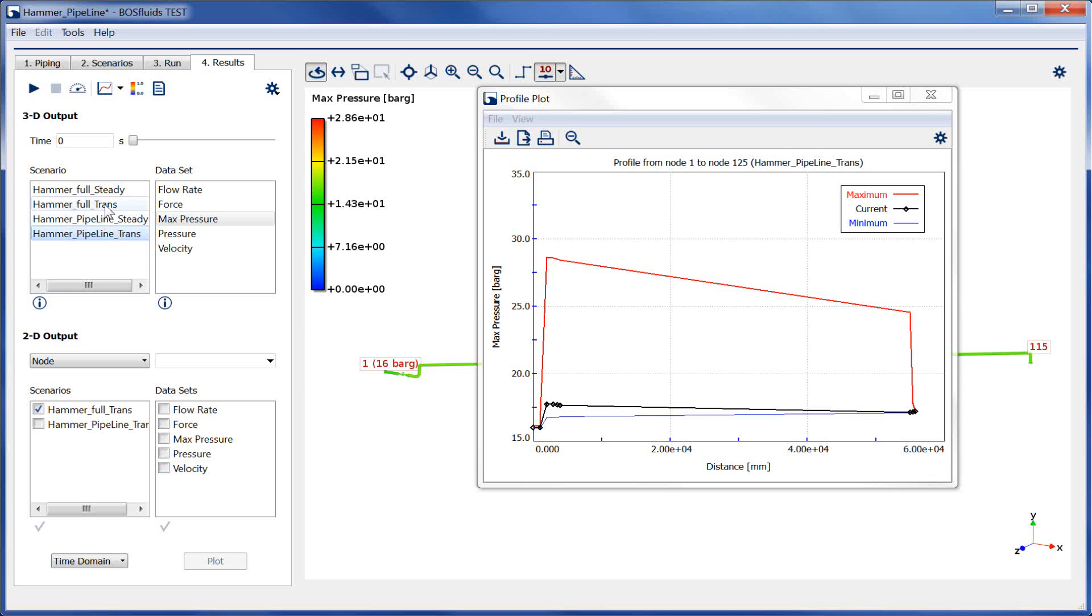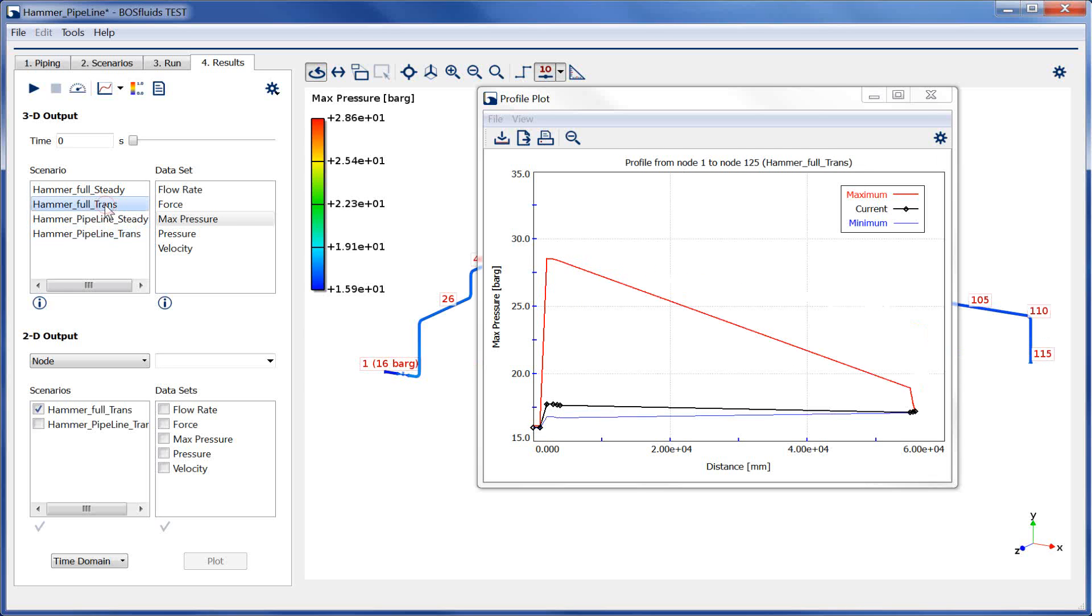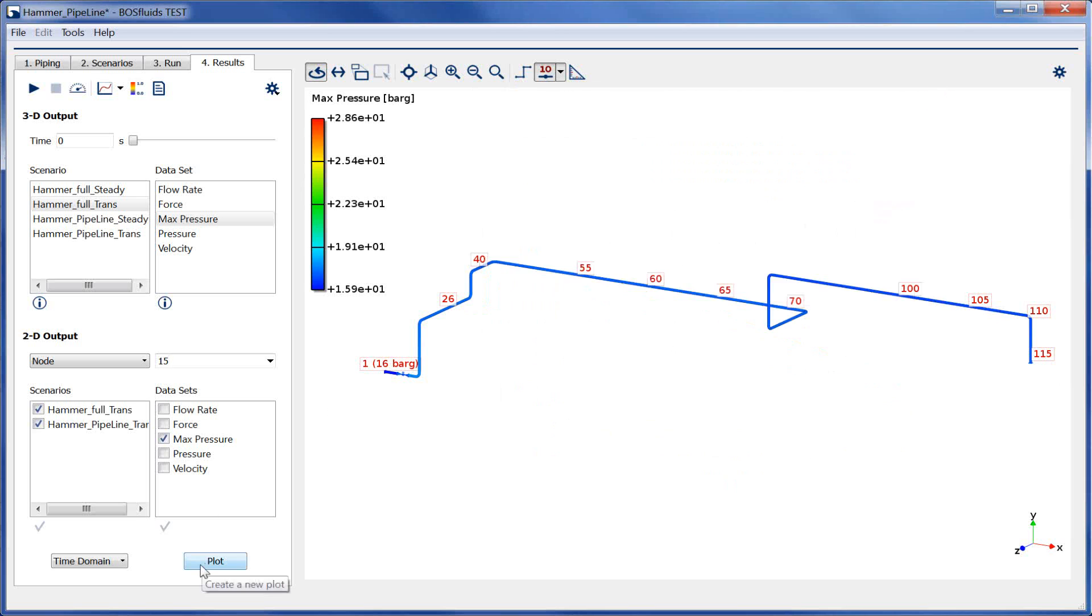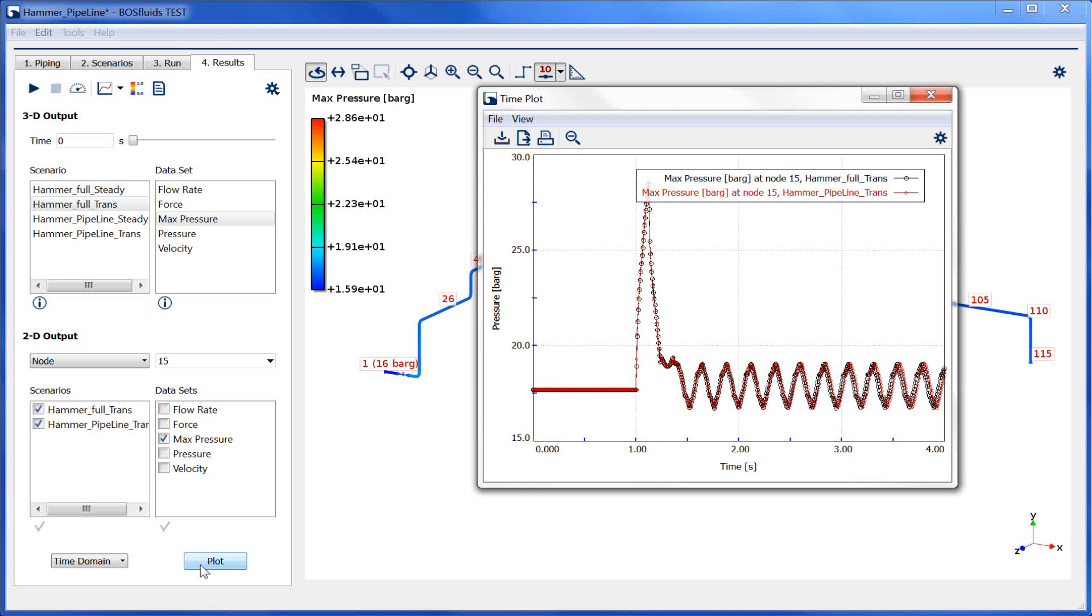We will verify this by plotting the max pressure close to the valve at node 15 for both transient simulations. It can be seen that the short term pressure peak is captured accurately even if only the pipeline element is used. The flow rate is also accurately calculated.